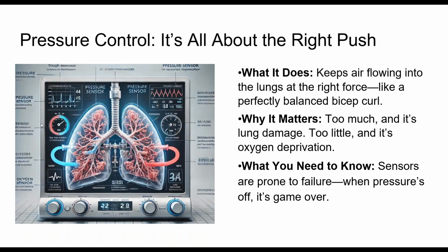Most ventilators have some level of pressure control, a minimal amount of pressure, say, when somebody inspires or expires, and a maximum level of pressure for when somebody expires or inspires. And before I forget, this is a good area to talk about: what if somebody coughs naturally? Most critical care ventilators have the ability to release a certain amount of pressure when a patient has their own force, if you will. And again, with a cough, you wouldn't want that backing up, blowing up their own lung instead of just coughing out like you could naturally.